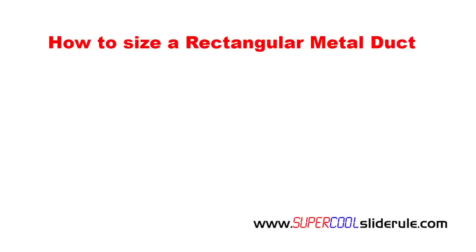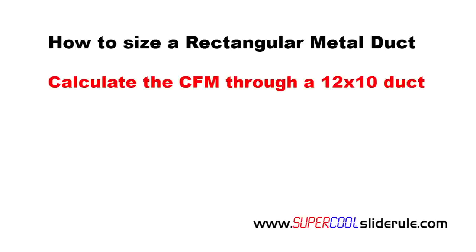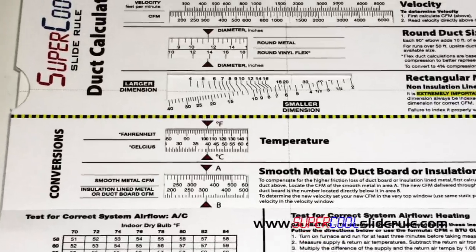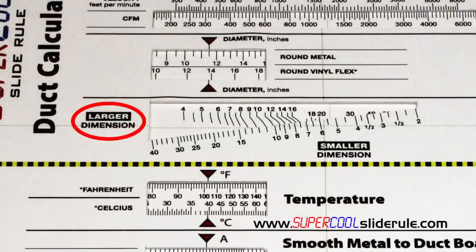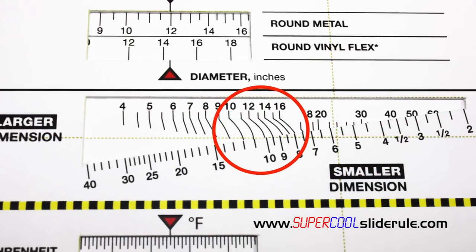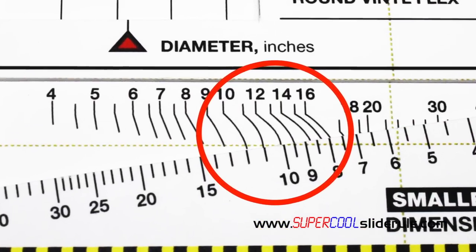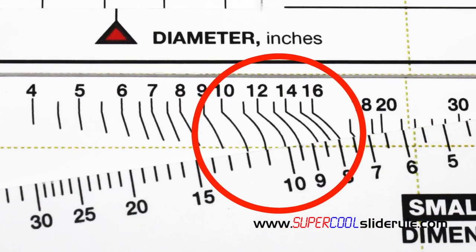There are many ways in which to use the duct calculator, but in this example we will calculate what the CFMs through a 12 by 10 duct will be. The most important thing to keep in mind is that the larger of the two dimensions will always be indexed over the small dimensions as seen here. So 12 is our larger dimension — it will be on top. We will then line up this line with the 10 like this.